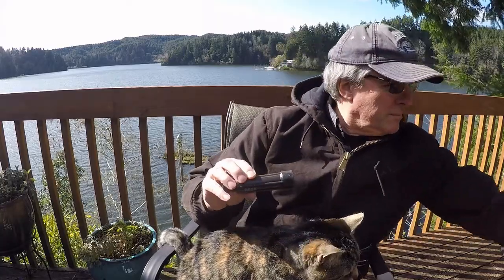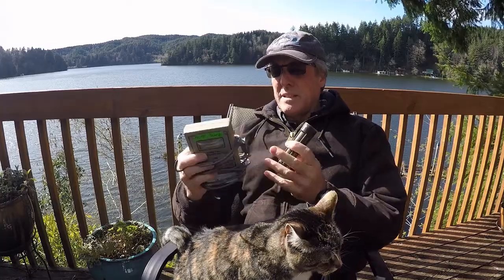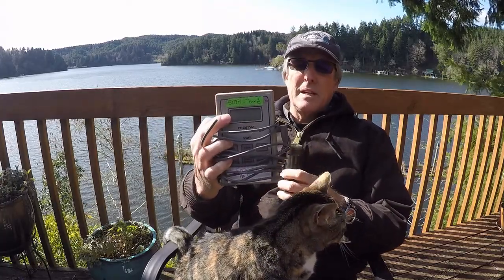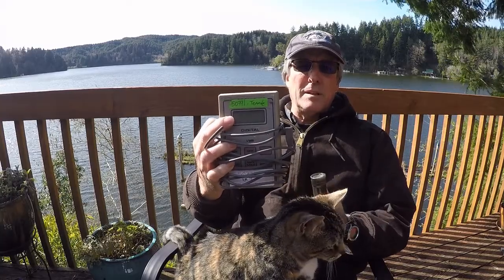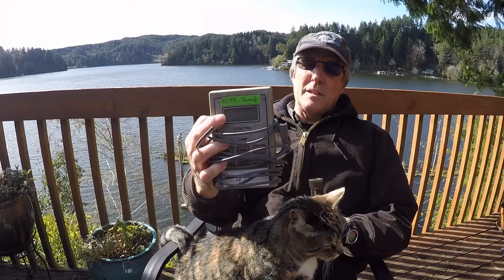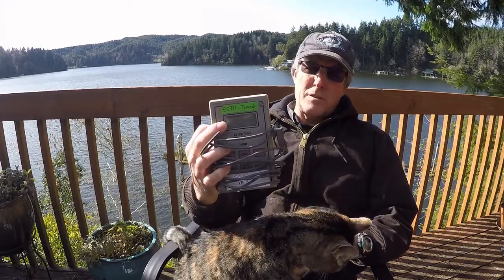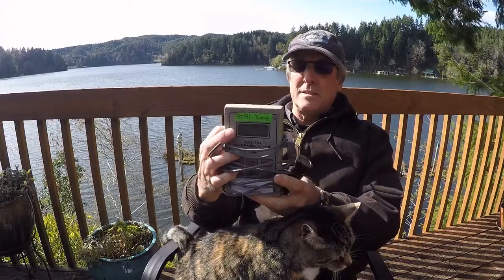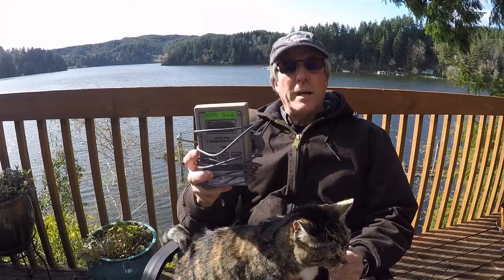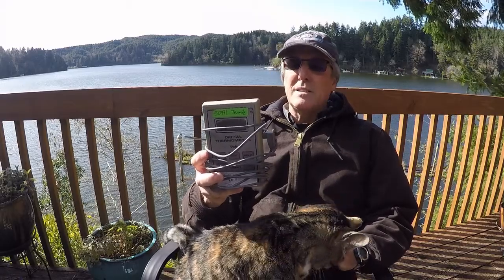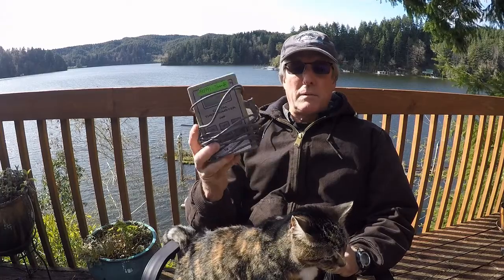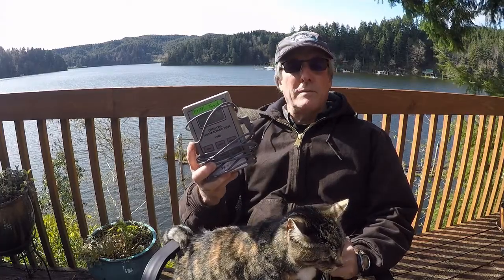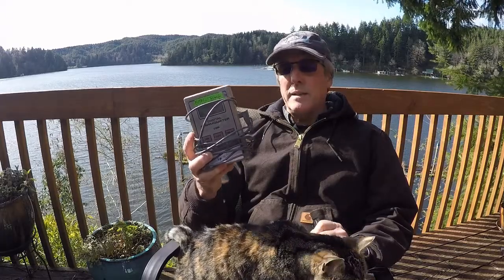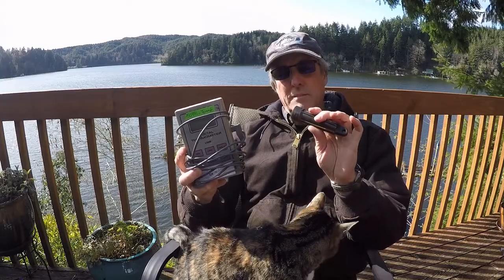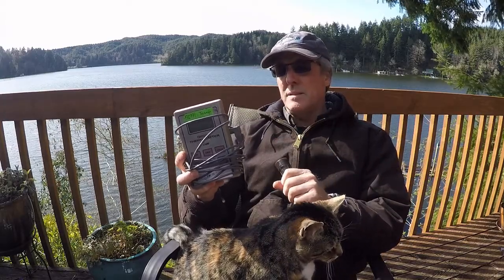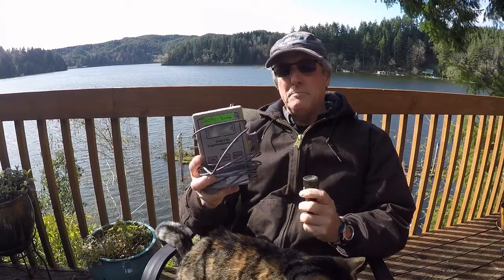You can also use other thermometers to get temperatures. This is a digital thermometer. In particular, this is a NIST thermometer, which is an indication that this particular thermometer has been calibrated and is within plus or minus 0.2 degrees centigrade. So whenever we're trying to calibrate something, we can rely on this. We send it back to the Department of Environmental Quality every year, and they recalibrate it and make sure that it's accurate. So if we're trying to see if this is accurate, we can compare it to the NIST thermometer and find that out.